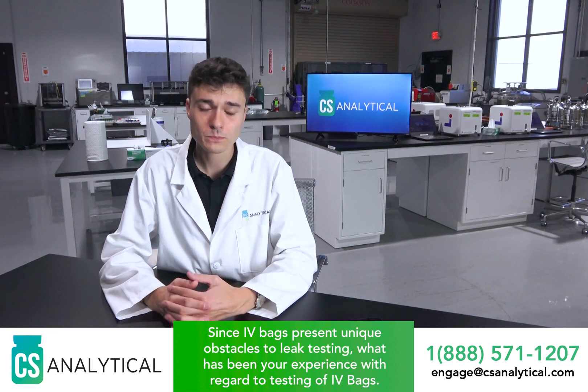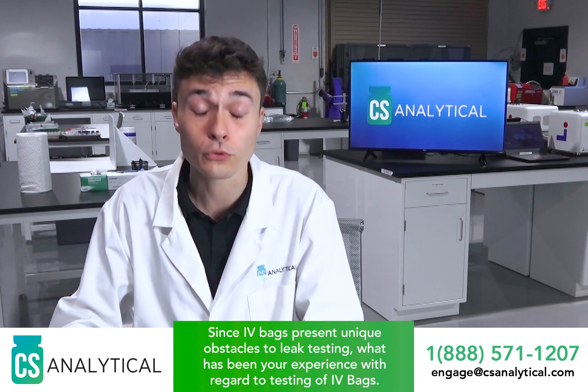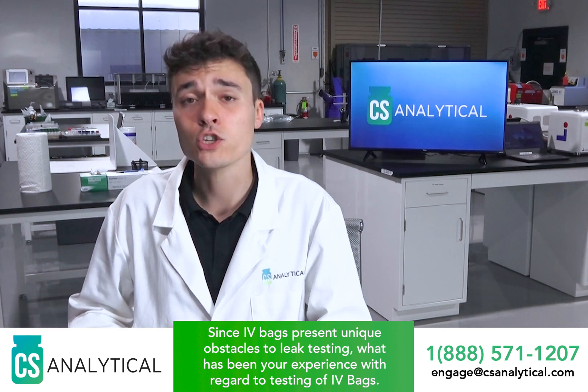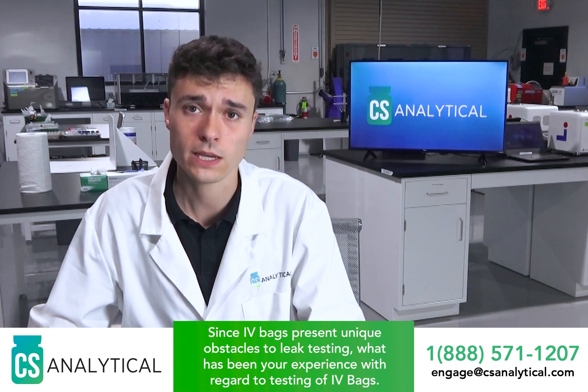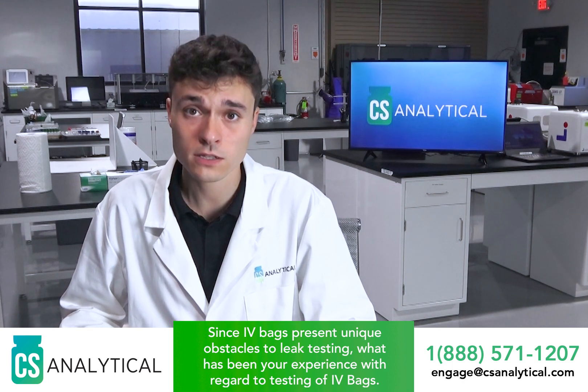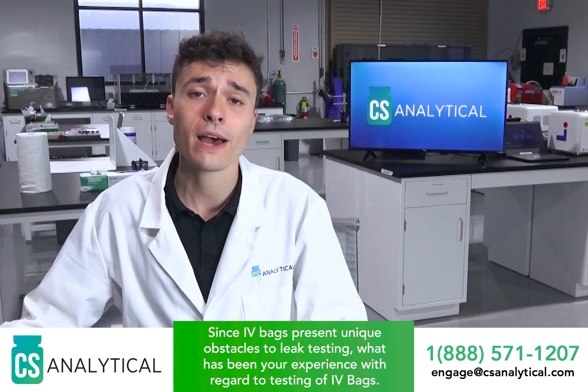So how do we go about overcoming that? This is an area of much development and a pretty hot industry trend right now. A lot of people are trying to evaluate and improve the available solutions for IV bag systems. Here at CS Analytical, we have a host of technologies to evaluate IV bag systems, and just like any other package system, it's a matter of evaluating which one is suitable for that specific use case. We do have vacuum decay systems with different chambers made for different size IV bags — typically custom designed for a client's specific product — so we can evaluate the feasibility of using vacuum decay for these applications, and then develop and validate if it is in fact feasible.